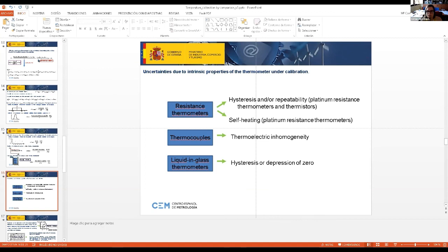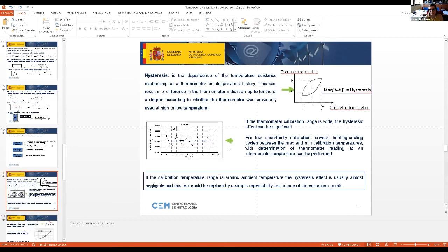If we talk about resistance thermometers, we have to be aware of the hysteresis and repeatability of these thermometers, and also of the self-heating. If we work with thermocouples, we have to know that the wires of these thermocouples are not homogeneous, so we need to check the inhomogeneity. And if we work with liquid in glass thermometers, we also have to know that they have hysteresis or depression of zero. What is hysteresis? It is a very easy concept: a material takes time to recover its initial state. That's the basic concept of hysteresis.